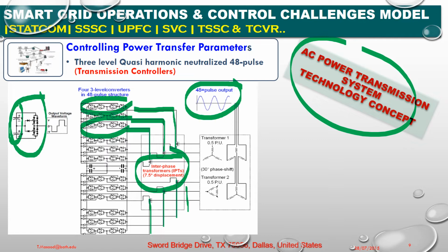Now, what we have to observe further here. The significant disadvantage of the 3-level converter is that with increasing conduction angle, an amount of third harmonic flows into the midpoint of the DC capacitor. This current generates a third harmonic voltage across the capacitor. In order to keep this harmonic voltage within acceptable limits, to avoid generation of additional harmonics in the AC output and an increase in the converter current rating, the size of the DC capacitor has to be increased compared to that of the 2-level converter.